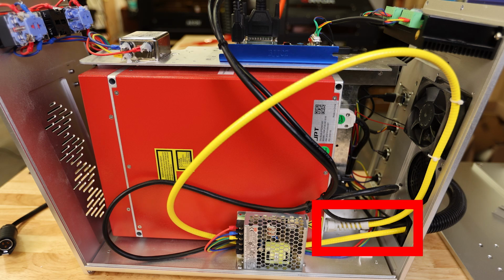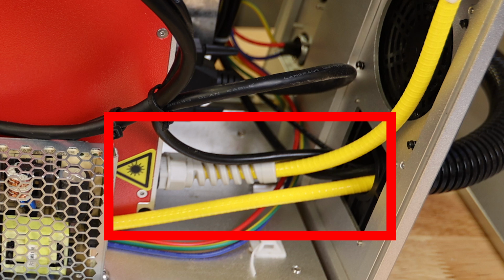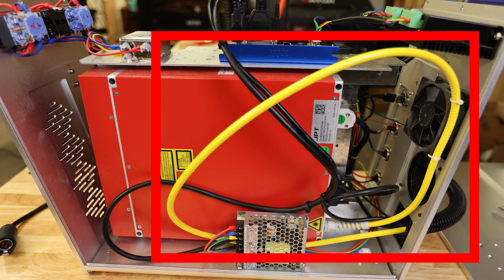The yellow cable here, though yours may be a different color, is your fiber optic cable that carries the laser to the galvo head. It's very important to never bend this cable. Fiber optic cables are typically made of glass and easy to break. Excess fiber optic cabling should be distributed in a large loop as pictured, rather than a tight coil. Fiber optics that are coiled tightly wear much quicker than those with larger bends.